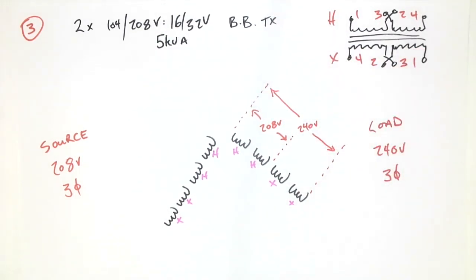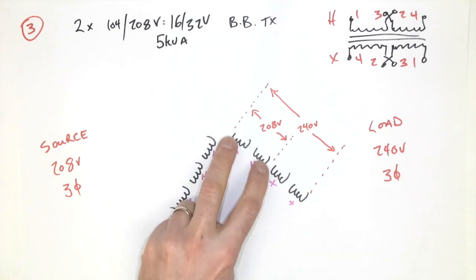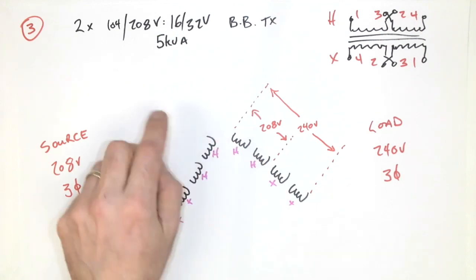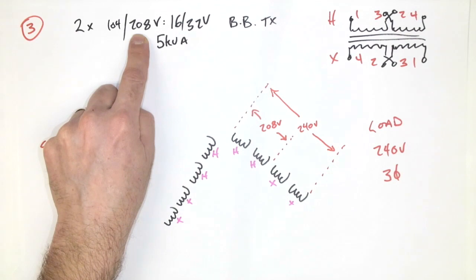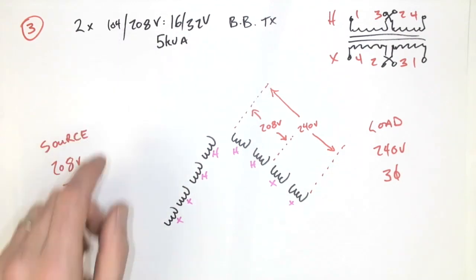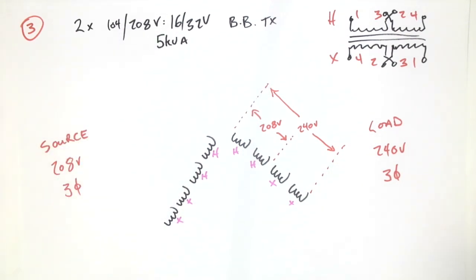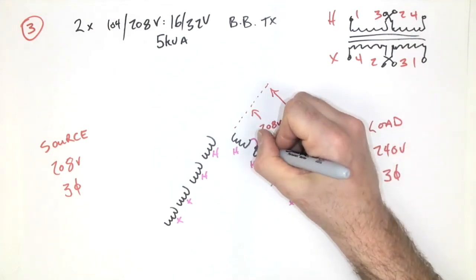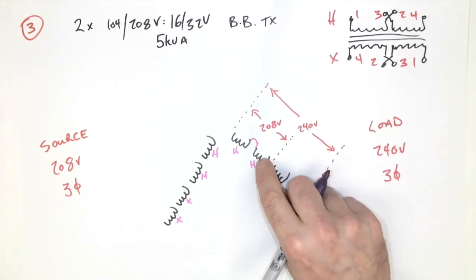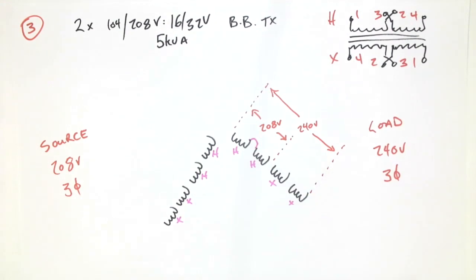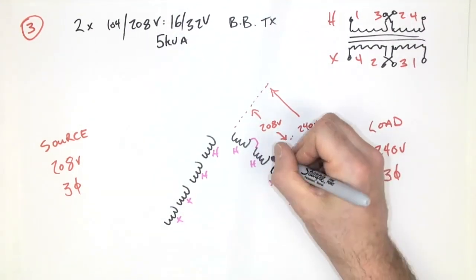All right, so 208 volt, it looks like I'm really restricted. I need to put them in series because each one of these windings is rated 104 volts. So I'm going to put those in series. And also, remember, we're doing an auto transformer connection, so the H and X windings right here need to be connected also in series.